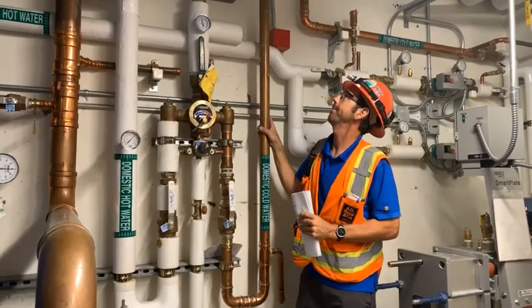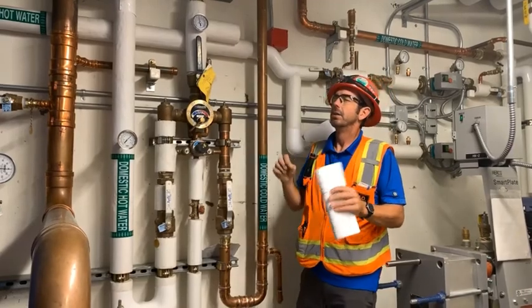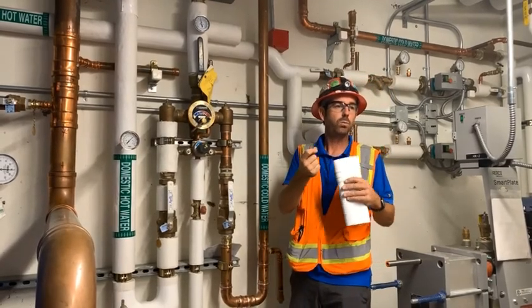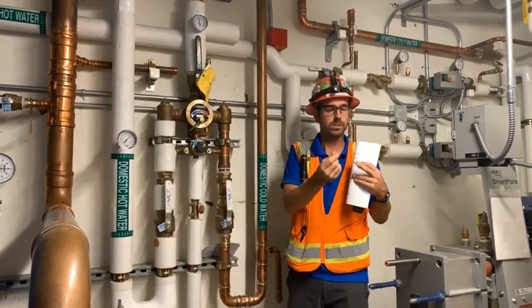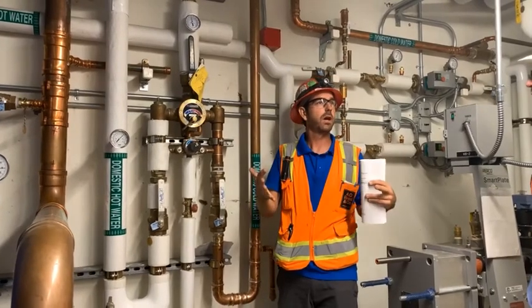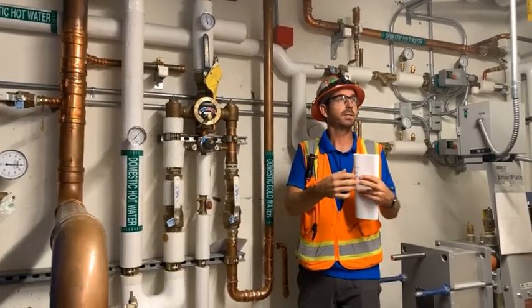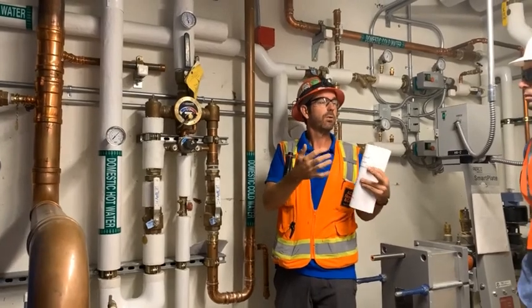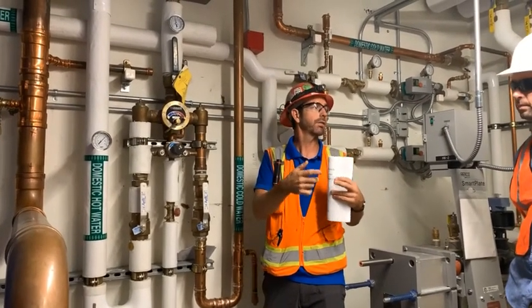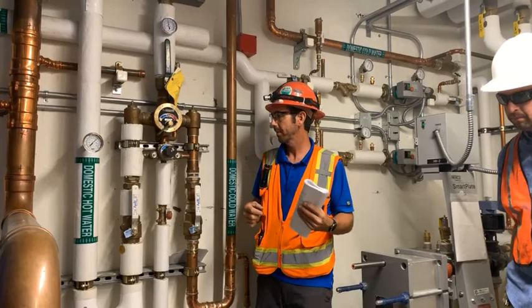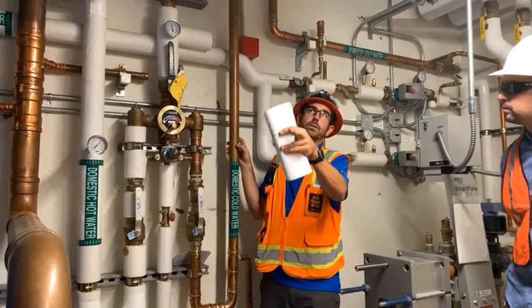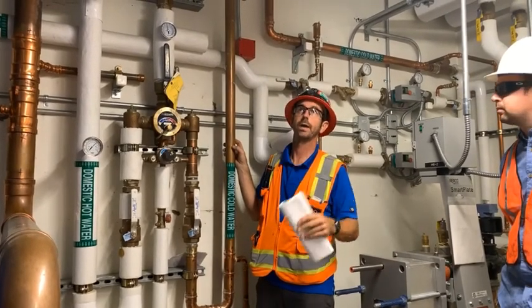I know that's a lot of information. So those temperatures, as they heat up, will start to expand. They don't ever close off. We can't ever have them close off. They always have to be sensing temperature. So there's always roughly 0.4 GPM running through that temperature set, okay? So it is important that the pump is running too for that.